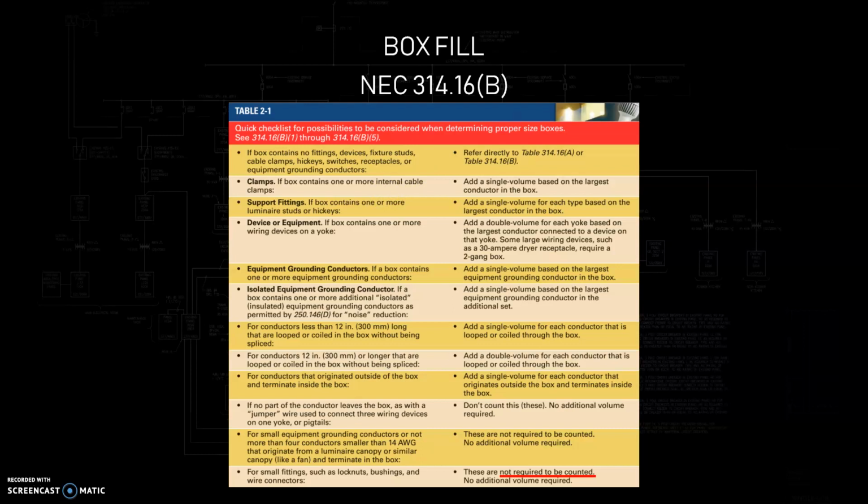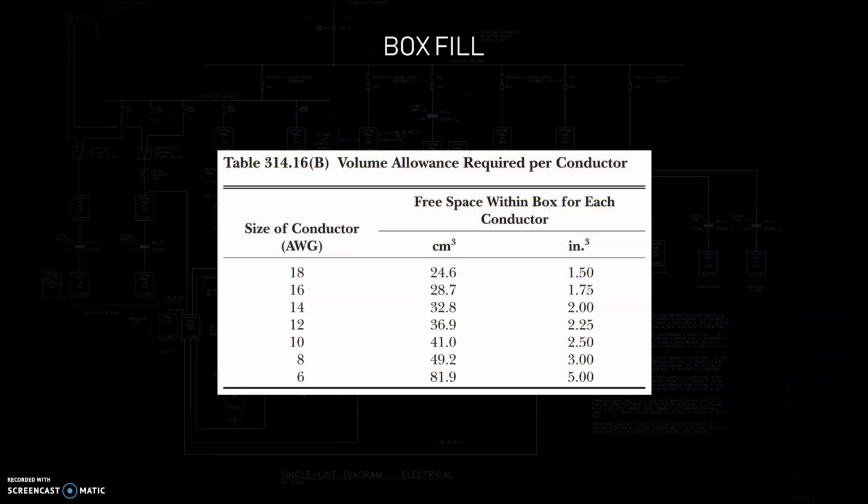That doesn't mean you shouldn't consider them. We know a large gray wire nut or blue wire nuts can actually take up a lot of space, but by code, we don't have to consider that. Another thing I want to mention, for your devices, for instance, I know that a GFCI is much bigger than a 15 amp switch, but by code, I can treat them the same. Doesn't mean I don't want to make some special considerations and say, you know what, I've got a GFI in here, I better leave some extra space. Again, the code is the minimum. Doesn't mean you can't go beyond it.